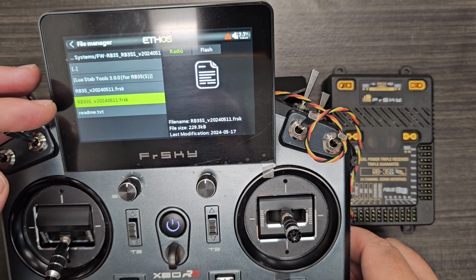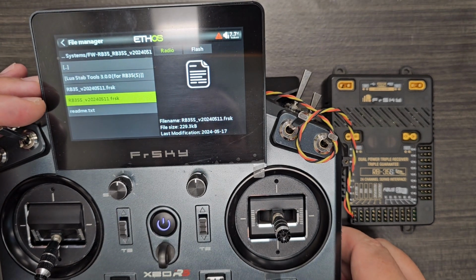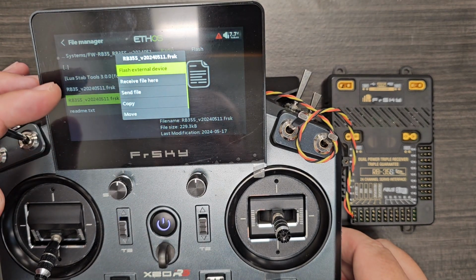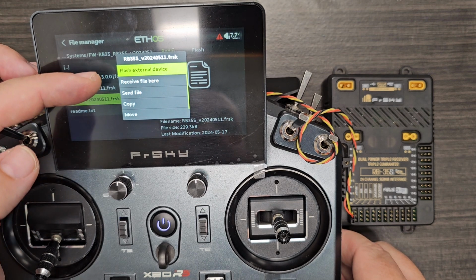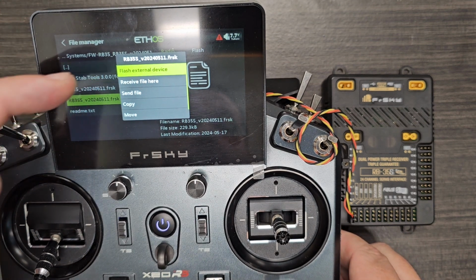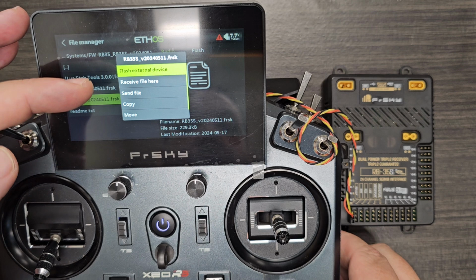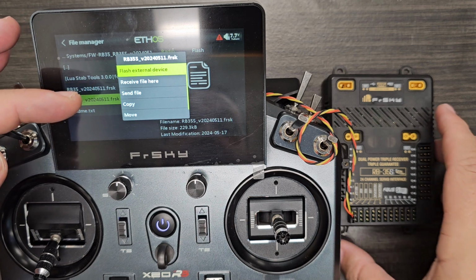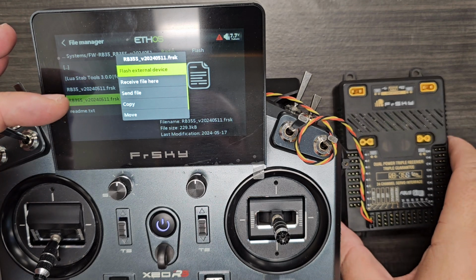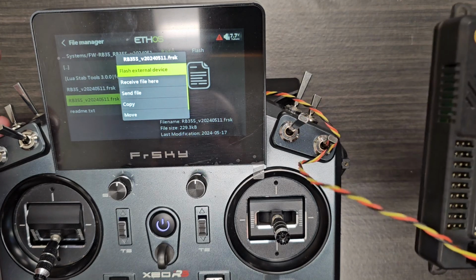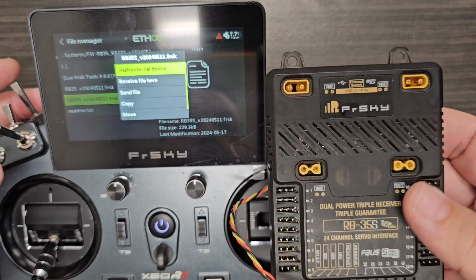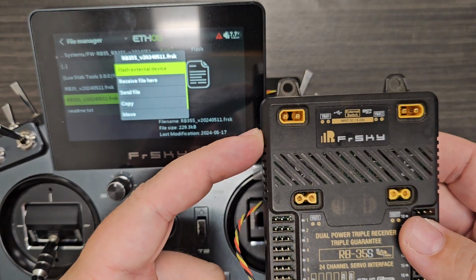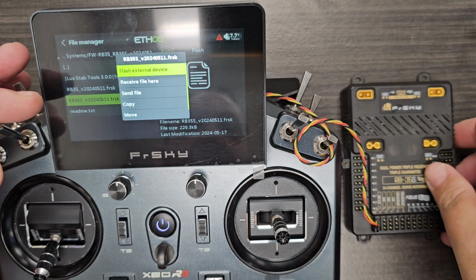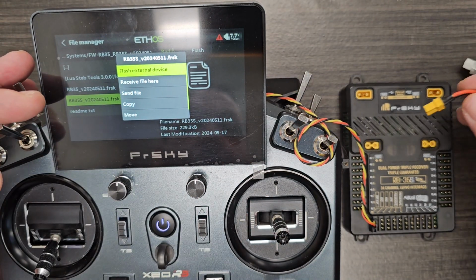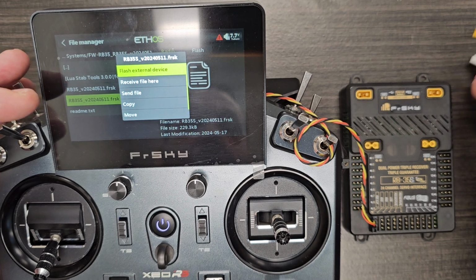When you click on the RB35S firmware file, it gives you these options, and we'll use Flash External Device. When you click Flash External Device, it will say Device Reset. The second important thing to remember is that the RB35S needs to be powered off, and when it says Device Reset is when you plug in the power to the RB35 unit.